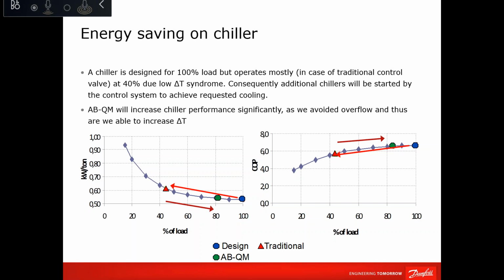So if we take an example here, in order to simplify the energy saving on the chiller, every chiller, let's say, requires a suction temperature on the compressor. And what the compressor will be doing is compressing the gas or the refrigerant to the condensing temperature. Let's say if we take 12 degrees entering the compressor, you need to heat it up to 40 or 42 degrees condensing temperature. Then the compressor will require, let's say, 0.7 kilowatt per ton to do that.